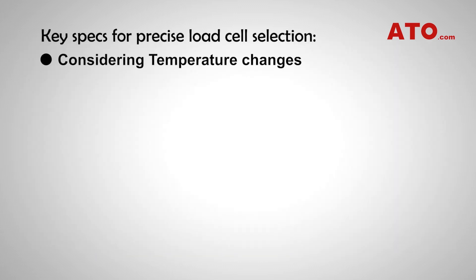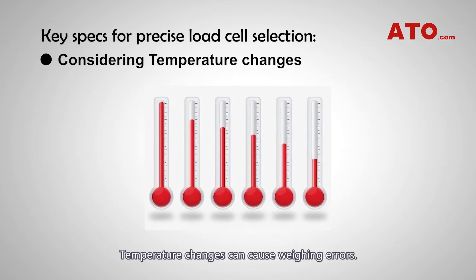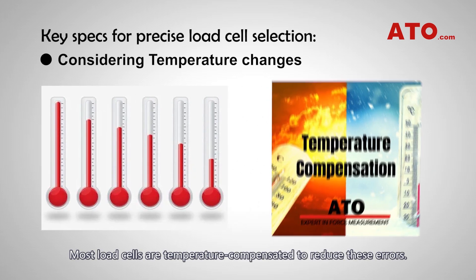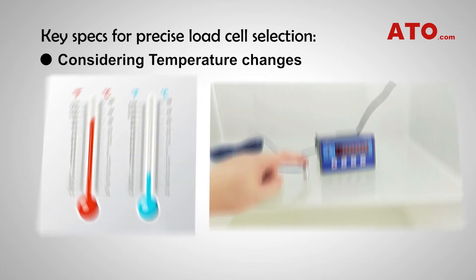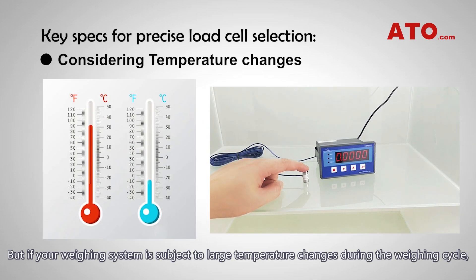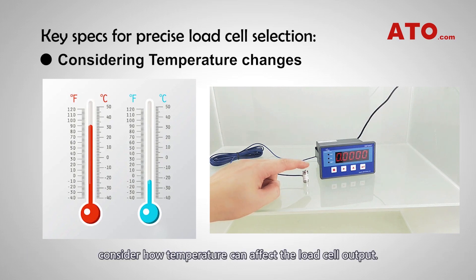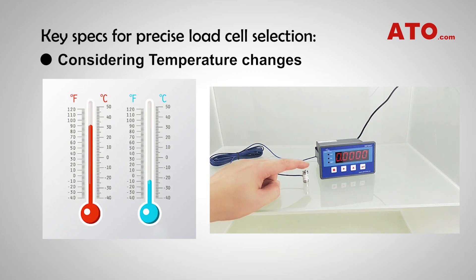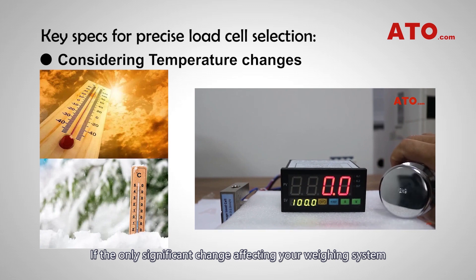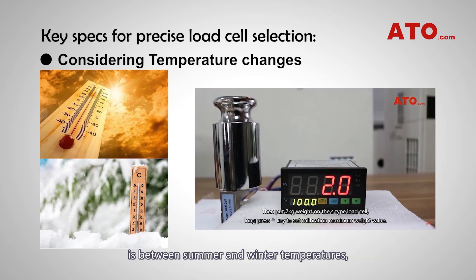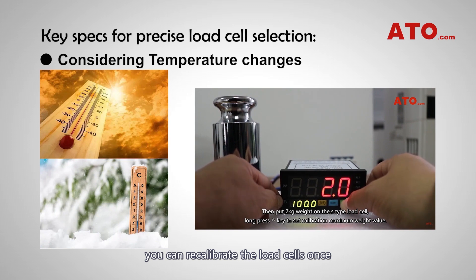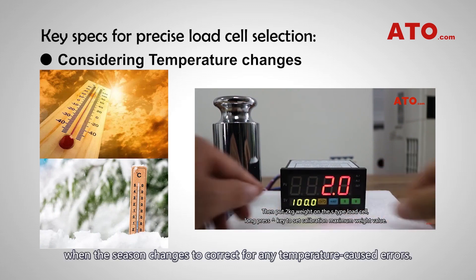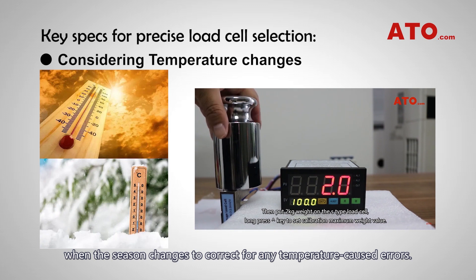Considering temperature changes. Temperature changes can cause weighing errors. Most load cells are temperature compensated to reduce these errors. But if your weighing system is subject to large temperature changes during the weighing cycle, consider how temperature can affect the load cell output. If the only significant change is between summer and winter temperatures, you can recalibrate the load cells once when the season changes to correct for any temperature-caused errors.